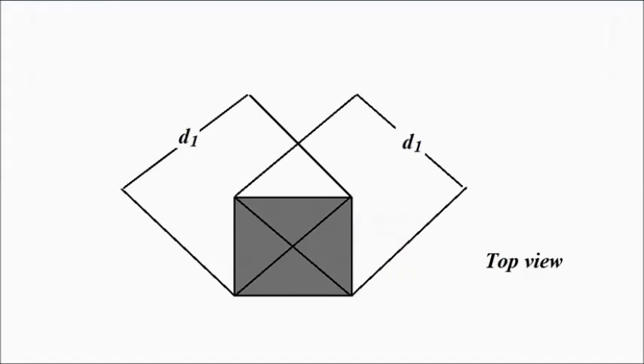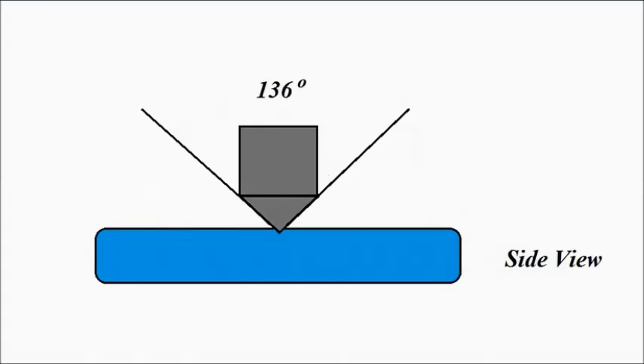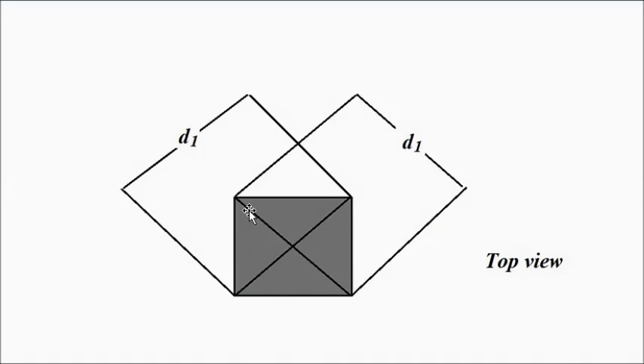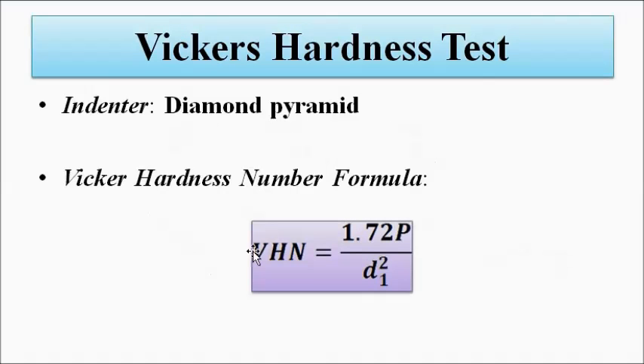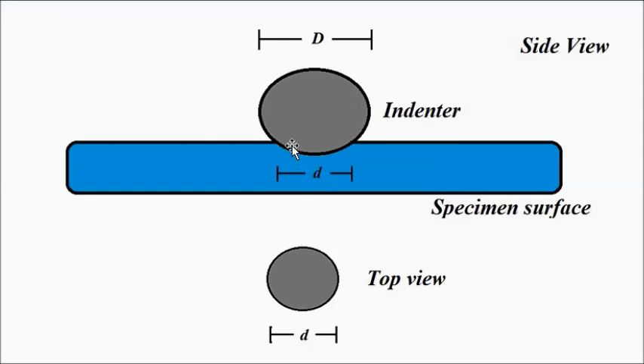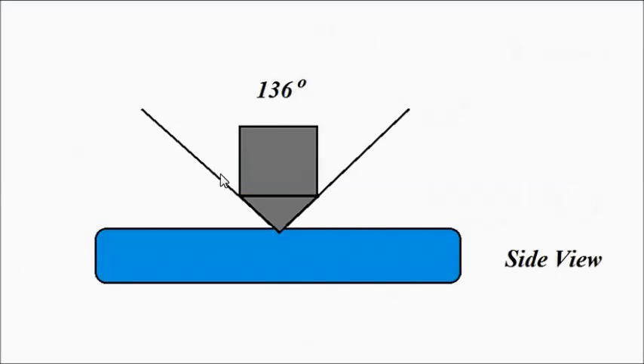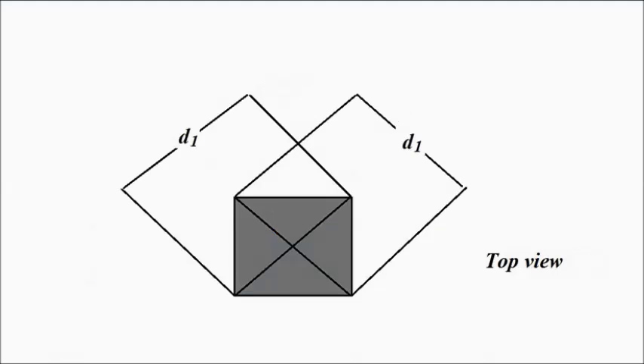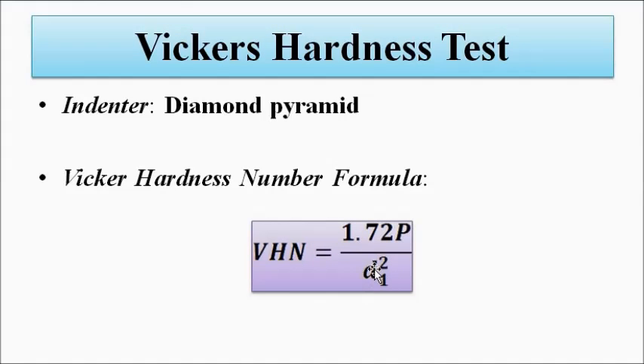An important detail for the Vickers test is the angle between the faces of the diamond pyramid indenter, which should be 136 degrees. The side view and the top view of the indentation should not be confused. In the Brinell test the indentation is circular (spherical indenter), but for Vickers, because a diamond pyramid is used, the indentation looks like a square from the top, and the diagonal length d1 of this indentation is critical for the hardness number calculation.